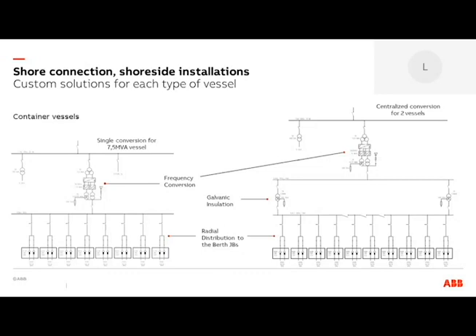So we can think of having one centralized frequency converter that feeds more vessels at the same time. It is common practice to dimension each galvanic insulation on shore for 7.5 MVA, while sometimes we can optimize the use of the frequency converter. For example, with a 15 MVA frequency converter we can feed two or more vessels, since real consumption is definitely lower than the standard value. It is also possible to eventually increase the size of the frequency converter at a later time.